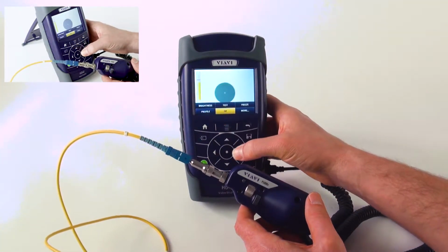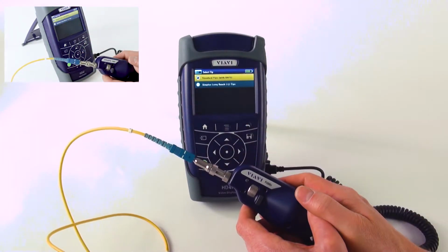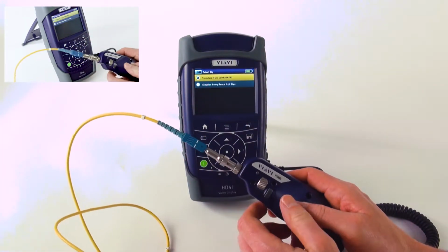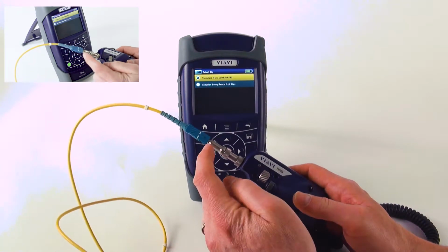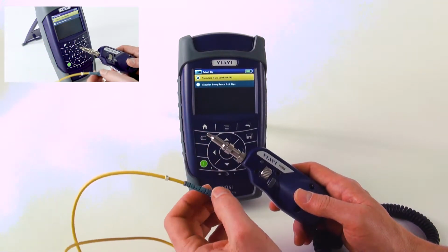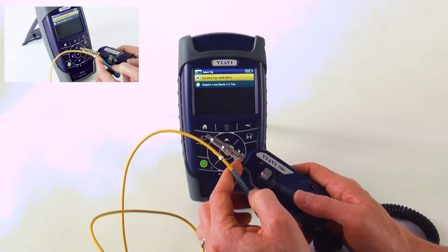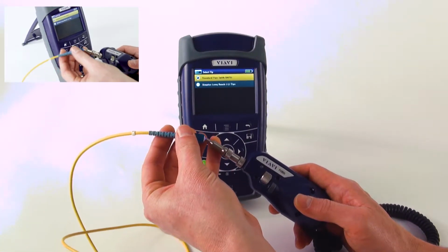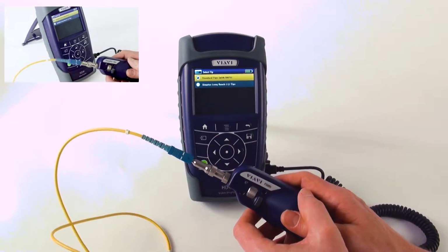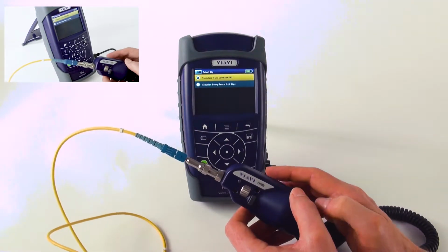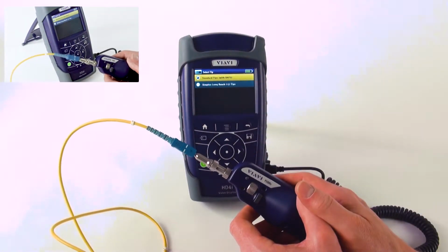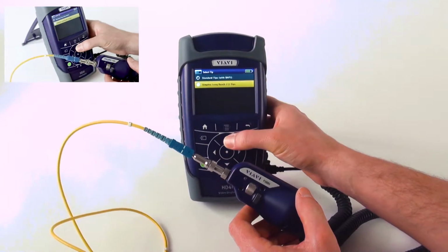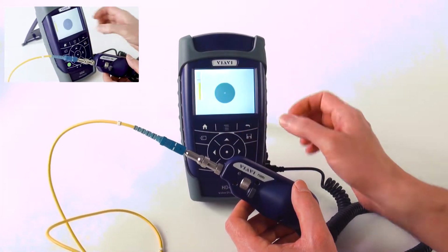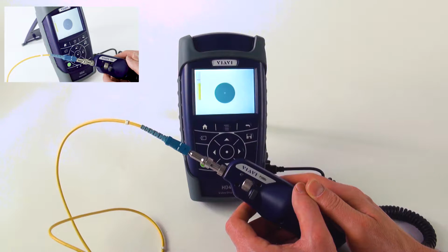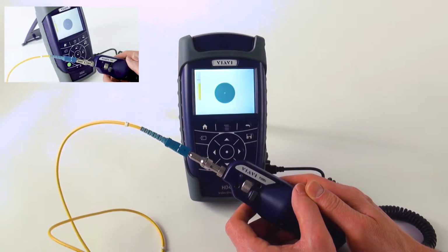Now I want to go into tip and just make sure that I have the right tip selected. Right now I'm using the most standard configuration. This is a standard tip with a BAP1 optical lens attached to it. So that's straightforward. There's other long reach tips and things that are available, and if I was using one of those, I would select that one, but I don't need to do that. I'm going to stick with what I have and select that. And now I'm ready to proceed forward with my test.